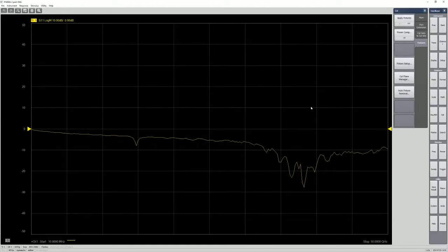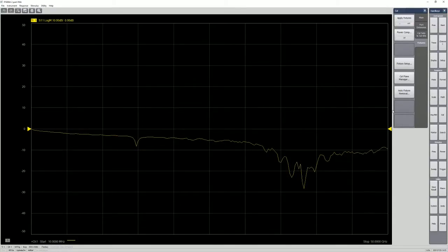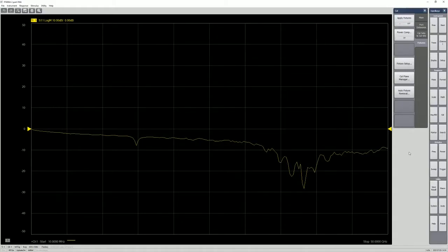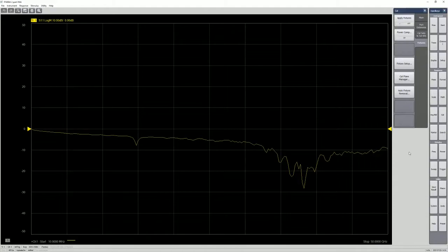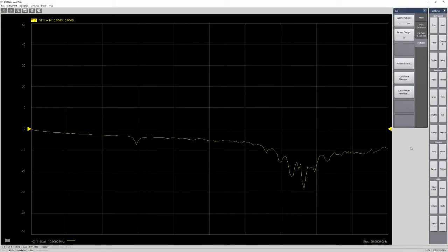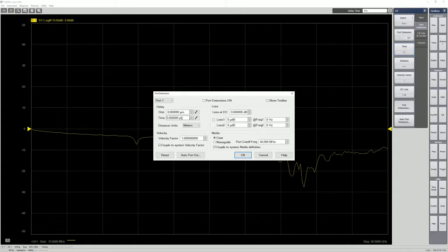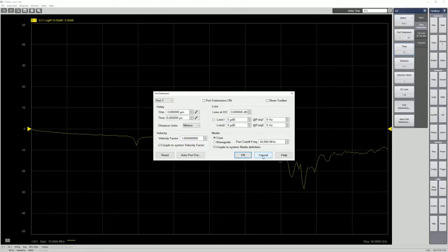So before going to auto fixture removal, there's another thing that I want to show you. It's called port extension. So what does it do? Back in the days, especially like for those old PNA-X, remember the four colorful buttons and also the fill forks. So we do not have auto port extension at the time. So we normally what we do is that we just go to port extensions and then change the value here until we meet a good open port.